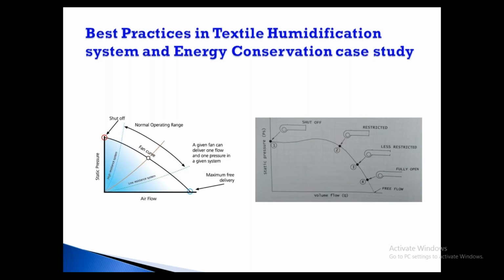As AMCA standards are there, the Air Movement and Control Association. There is a particular testing standard for testing the fan efficiency, flow and pressure. There are different standards and methods. You have to collect standard ducts of 2 meters, 3 meters at the inlet. Then you have to put a pitot tube to collect the information on total pressure and static pressure, all these things. Then you have to arrive at this much diameter of the duct with this much velocity of air at the time of what is being created, like the fan manufacturer has to do.